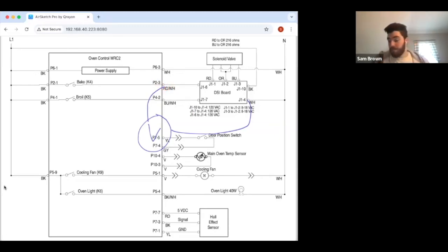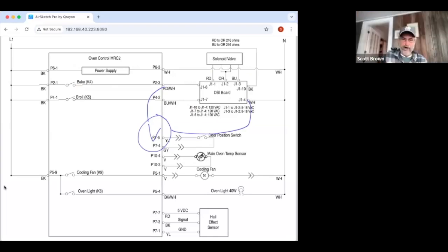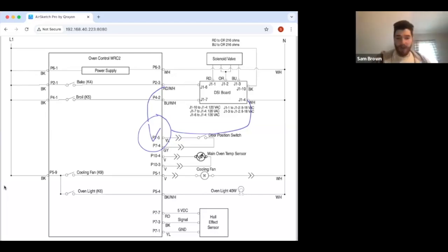And because he had eliminated everything else, the DSI board was working properly, the temperature sensor was in spec, the only thing left was to replace the main control board. That's sometimes what you get, is that you get to the main control board after you've eliminated all the other possibilities. This is called backing into the solution. So, process of elimination. You've eliminated everything else, so you're only left with the one thing. Yep. And as it turns out, that was in fact the problem. It started working properly after the main control board was replaced.